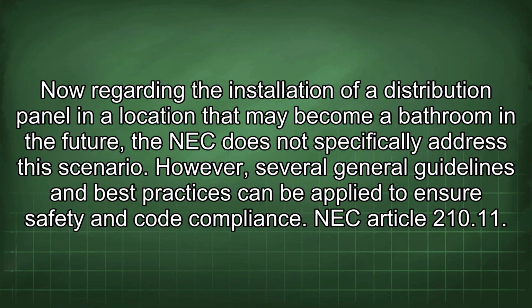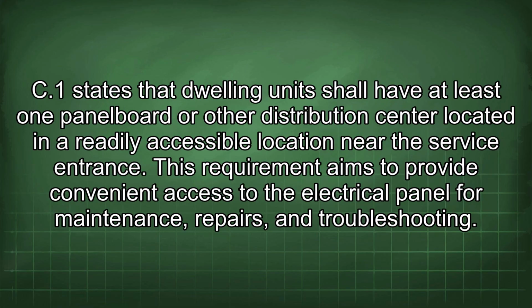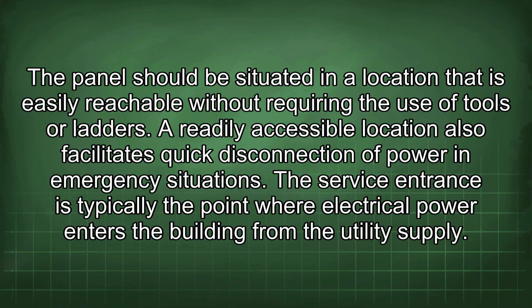NEC Article 210.11.C1 states that dwelling units shall have at least one panel board or other distribution center located in a readily accessible location near the service entrance. This requirement aims to provide convenient access to the electrical panel for maintenance, repairs, and troubleshooting. The panel should be situated in a location that is easily reachable without requiring the use of tools or ladders. A readily accessible location also facilitates quick disconnection of power in emergency situations.